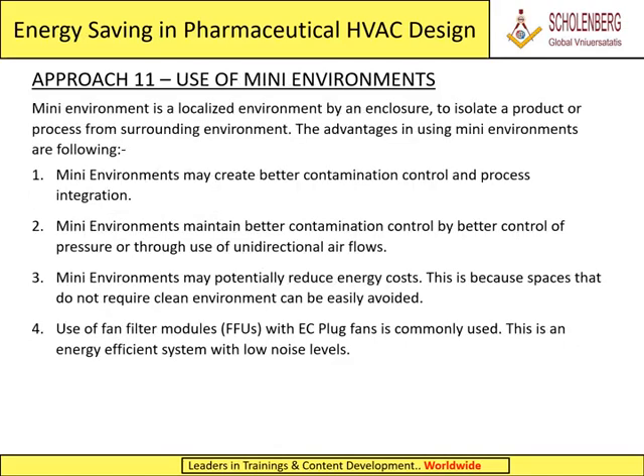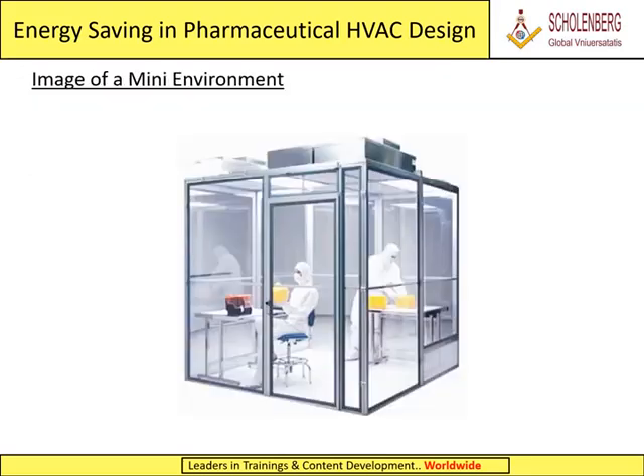Approach 11, Use of mini environments. A mini environment is a localized environment created by an enclosure, to isolate a product or process from the surrounding environment. The advantages in using mini environments are the following. 1. Mini environments may create better contamination control and process integration. 2. Mini environments maintain better contamination control by better control of pressure or through use of unidirectional airflows. 3. Mini environments may potentially reduce energy costs. This is because spaces that do not require clean environment can be easily avoided. 4. Use of fan filter modules, FFUs, with EC plug fans is commonly used. This is an energy-efficient system with low noise levels. Image of a mini environment.